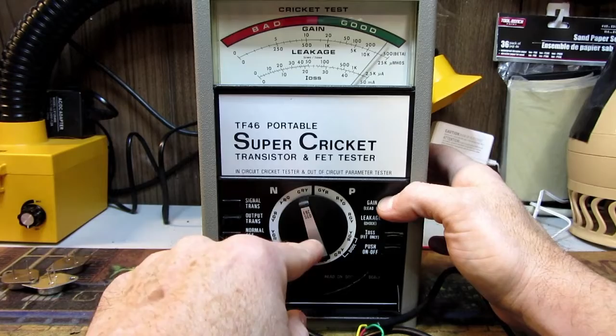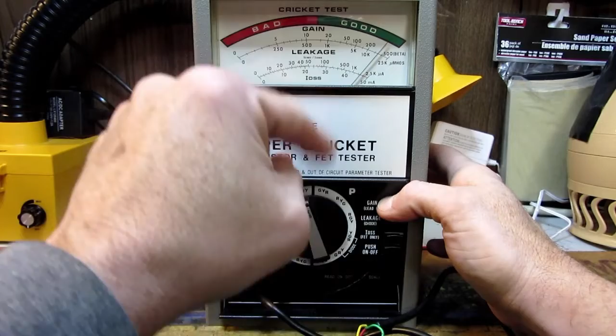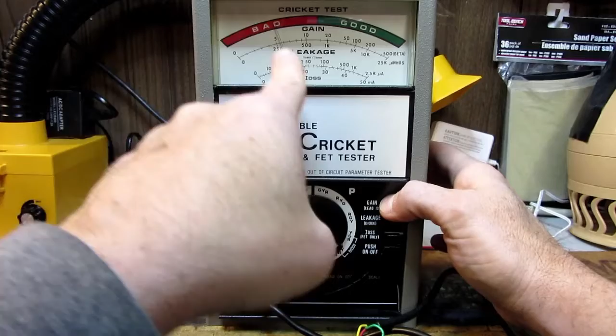So next you will press that in and you will hit gain. You're going to do this for both positions of the switch where you were getting the audible indicator. And only the higher of the two readings is accurate. So now you can tell right here this is going to be the accurate position because we're getting a reading of 350. If we go back to the other position, we hit gain, we're getting a much lower reading. So the correct reading for this is 350. It's the higher of the two readings.